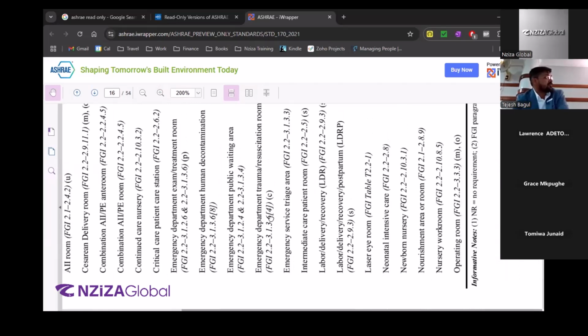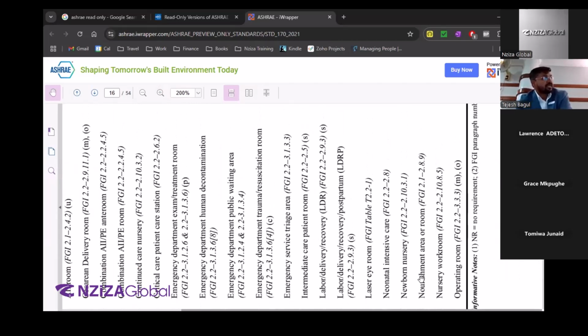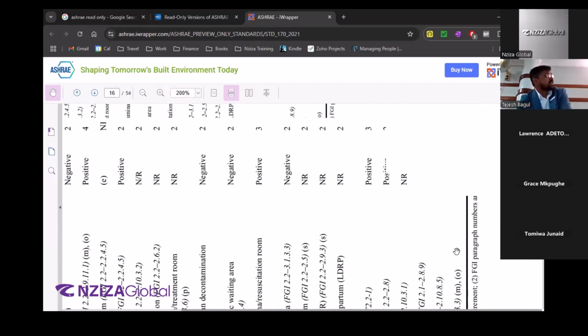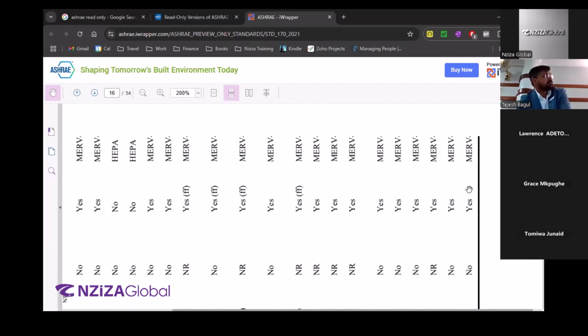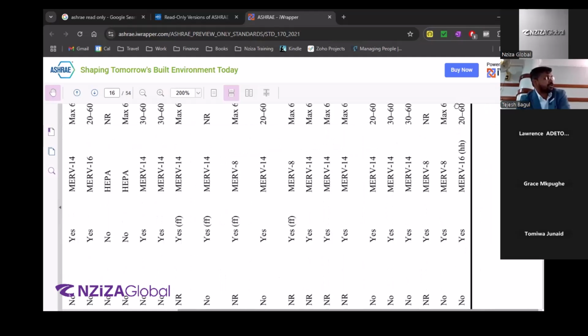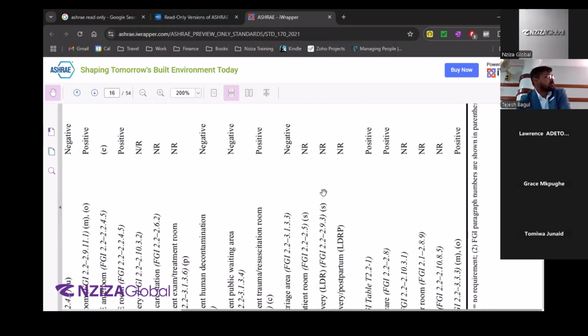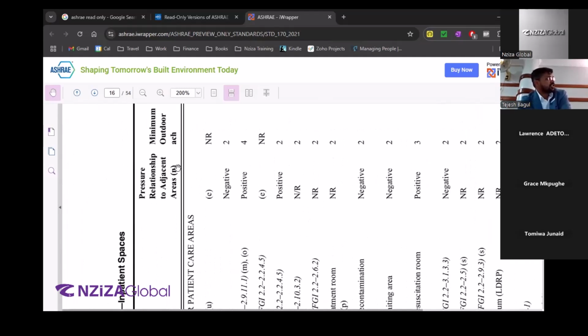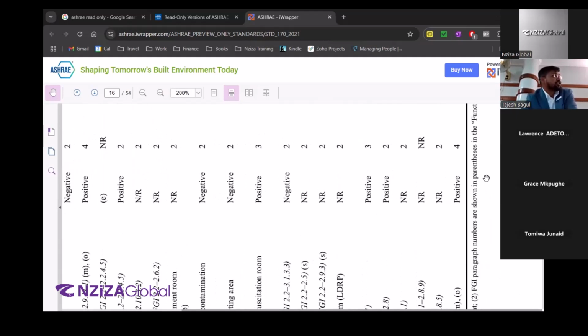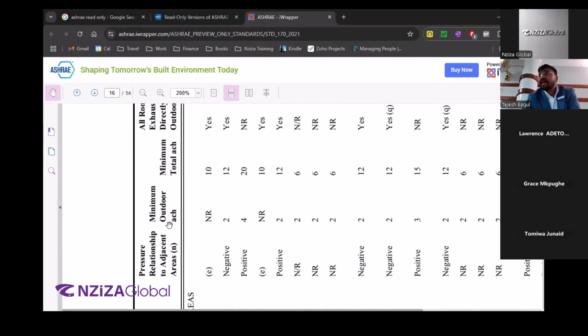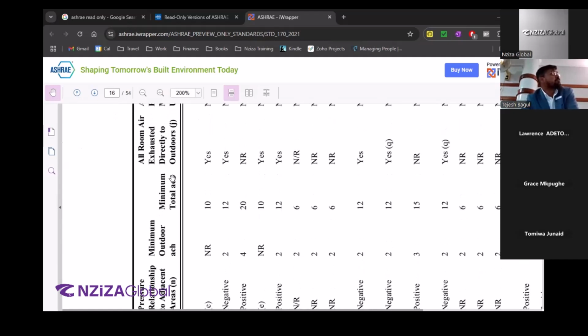Then we have the emergency department, but you need to find out something called an operating room. Now I've given you a straight answer over here. There is an operating room over here, the same operating room that you took a picture of. Now this operating room, if you check there, it has different parameters. Okay, this last row is for operating room, which has different parameters. And if you go up the column over here, you'll have pressure relationship to adjacent areas, right? So you check what this is, and then we will write down in the table that we have. All right. Just like that, you have minimum outdoor ACH, air changes per hour. You have the minimum total ACH, minimum total air changes per hour.